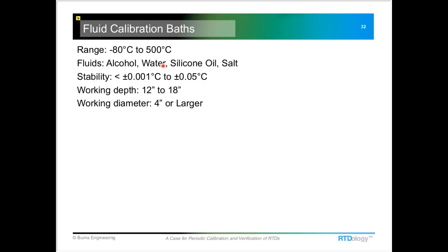Water should really only be used in an ice bath. Trying to use it at other temperatures, like if you're trying to hit it at a boiling point, that's dependent on your elevation above sea level. If you're at sea level, yeah, it might be an okay way to do it, but really prefer oil or a salt bath, and then done by comparison.